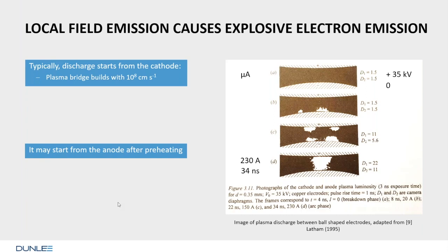Coming back to this local field emission, which causes EEE. Here I copied, I've stolen, a picture of a book from Latham, a very nice one. It would be great to read that for you. Latham in 1995 already depicted a vacuum gap, plus, minus, and black in between. Nothing in between, fine. 35 kilovolts applied, very narrow electrodes, okay. What he saw was that in the next step, some nanoseconds later, a cathode flare appeared. So the cathode started with something on 2 spots, left and right. A little later, the anode responded.